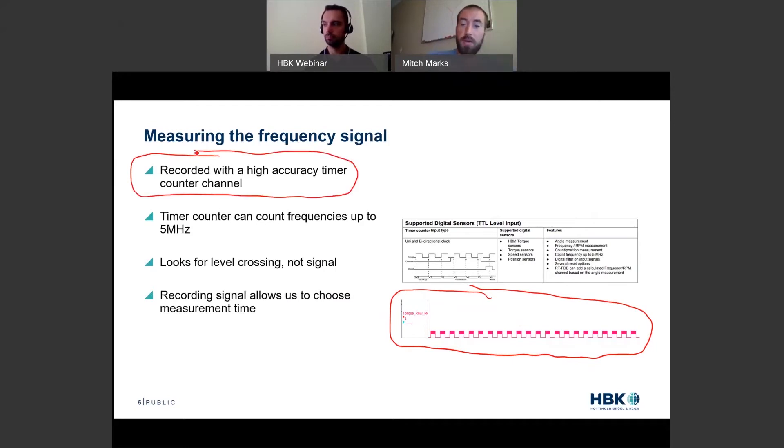In order to measure the frequency signal, we need to understand it a little bit. In this graph on the bottom here, we have this pulse train - a digital representation of that square wave coming out of the torque sensor. We can see that we have a pulse train with a frequency. This is actually a recording of the frequency output of the torque sensor. We record this signal with a high accuracy timer counter channel. That timer counter can measure up to 5 megahertz, so the 60 kilohertz isn't even scraping the surface. It's looking for rising edges. We're not looking at signal, we're looking at rising edges because it's digital. By recording this measurement period, this allows us to choose our measurement time. This is just a snippet from our data sheet about that timer counter channel and what it can be used for.